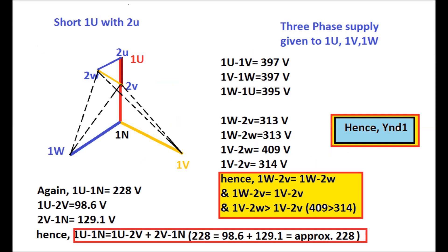A three-phase supply has been given to terminals 1U, 1V, and 1W. The measured phase-to-phase voltages are: 1U to 1V = 397V, 1V to 1W = 397V, and 1W to 1U = 395V. By means of the multimeter, the voltage between 1W and 2V is measured as 313V.